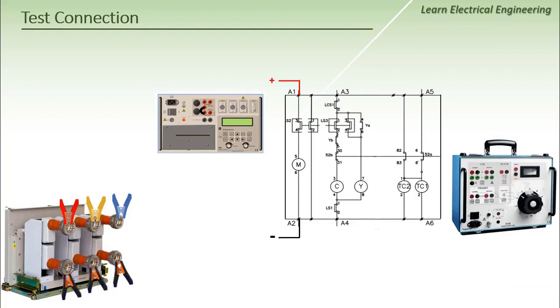Of course, it is possible, but I have a problem. What is it? We mentioned that the closing time and tripping time tests are conducted at different levels of control supply voltage, such as 100%, and in cases of under voltage and over voltage. For example, I do the closing time at 85% and 110% of the control supply voltage. As for the tripping time, it works at 70% and 110% of the control supply voltage. So now I can't use the control supply voltage that I have in the panel, so I will go and get an external power supply unit like the B10E device from Megger.